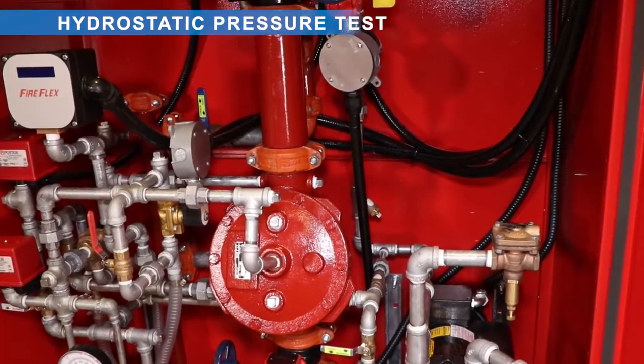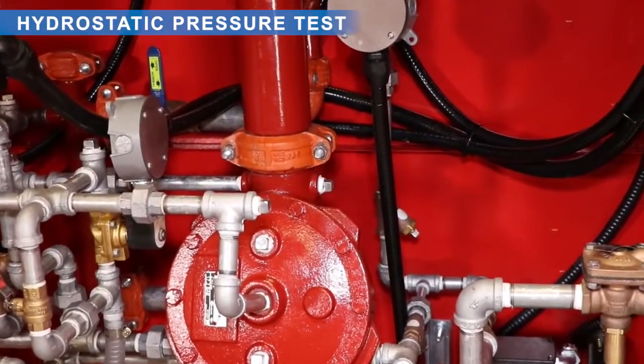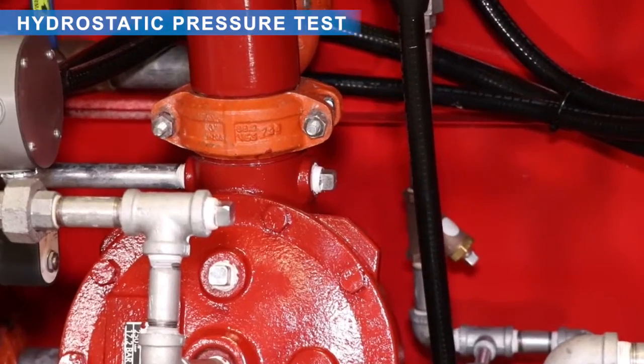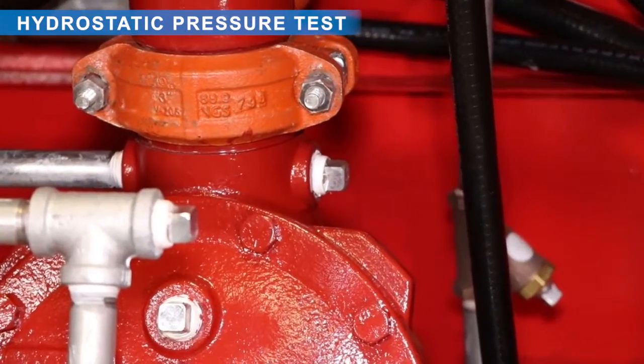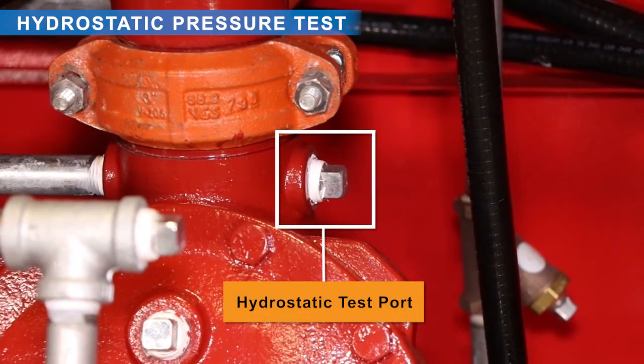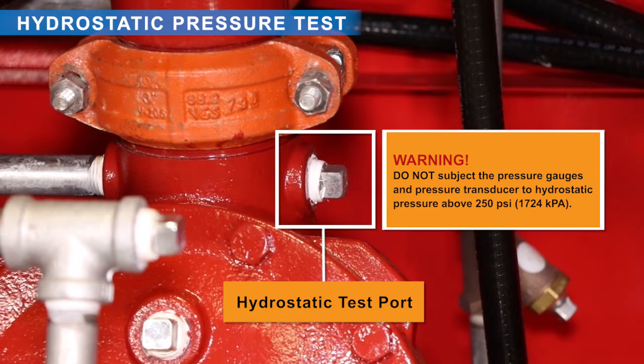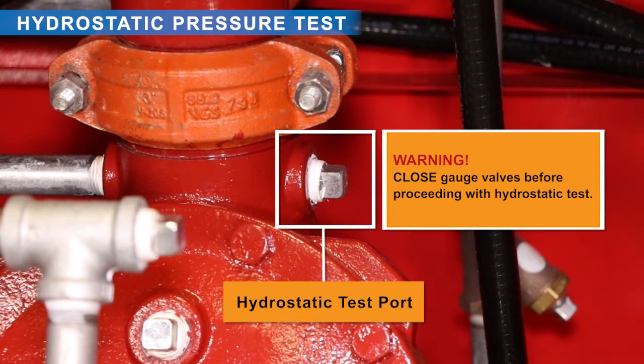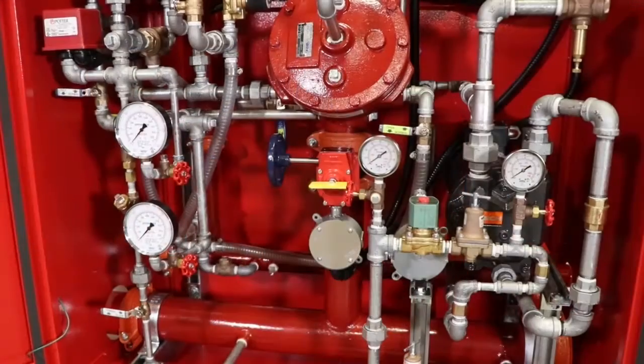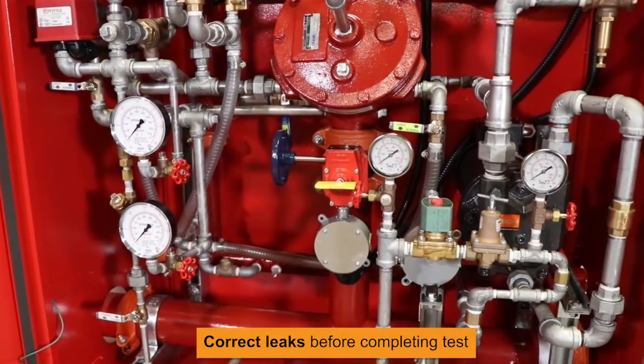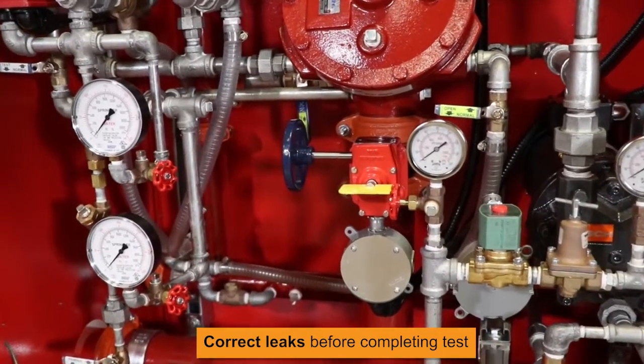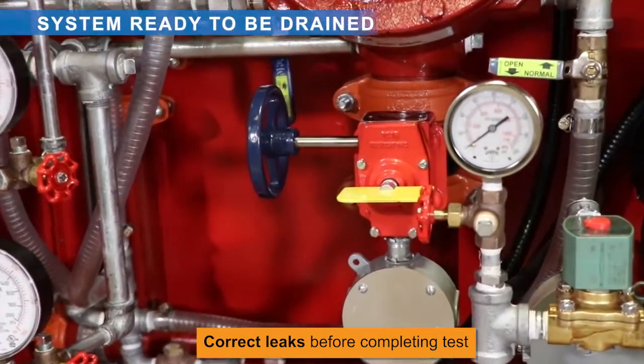Using the built-in contractor's hydrostatic test ports, fill vacuum sprinkler piping with water and maintain pressure as per NFPA 13 requirements. Do not subject the pressure gauges and pressure transducer to hydrostatic pressure above 250 psi. Close gauge valves before proceeding with hydrostatic test. If required, correct leaks before completing test. The system is now ready to be drained.